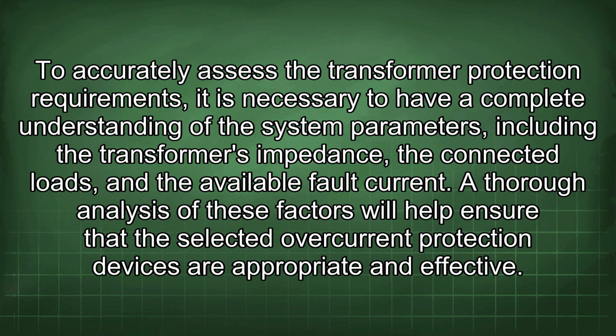To accurately assess the transformer protection requirements, it is necessary to have a complete understanding of the system parameters, including the transformer's impedance, the connected loads, and the available fault current.